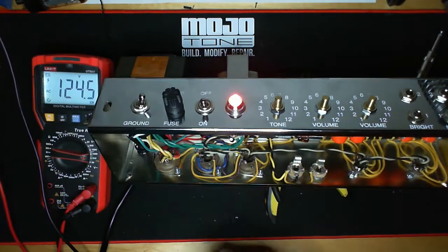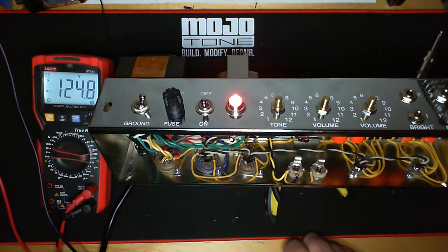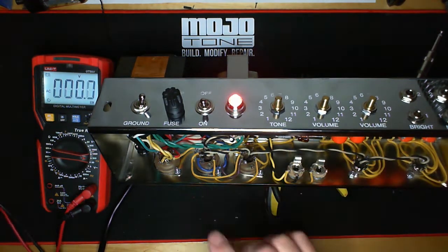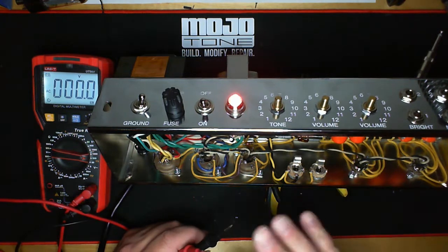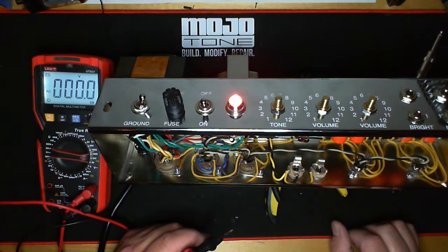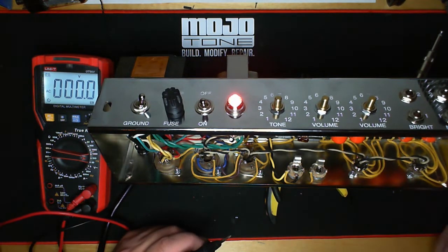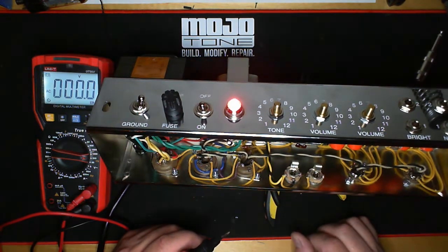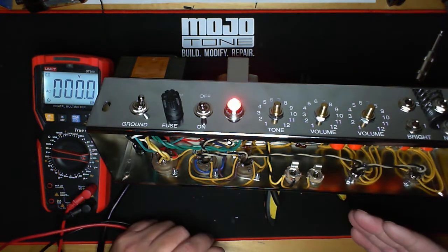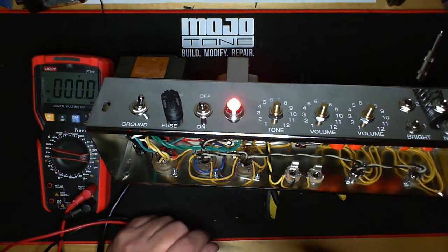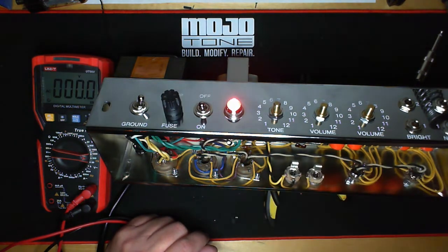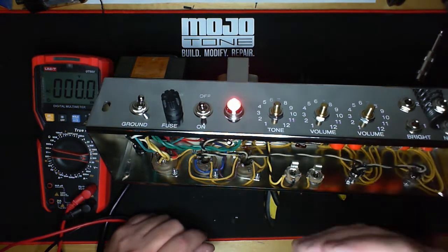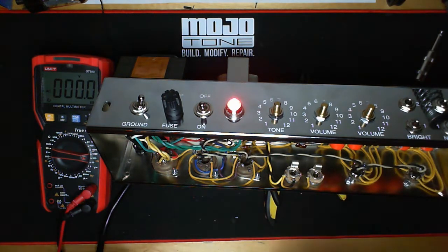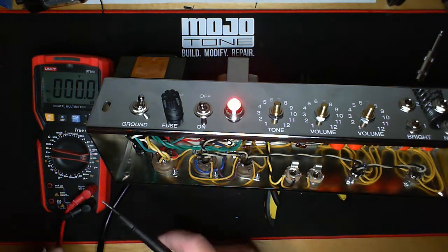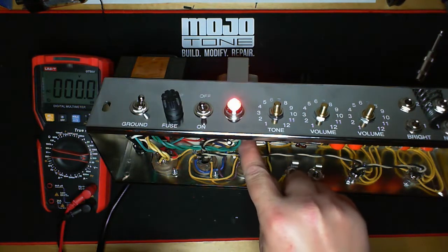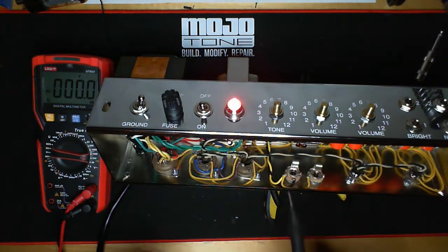I run almost 125 volts here, so that's going to elevate everything on my secondaries, and I need to be mindful of that when I'm looking across the board. That basically means that already, because the voltages are unloaded, they're going to be 10% higher than what they are. Then add an extra 1-2% because I'm about 5 to 6 volts over where I should be for 120 volts. This is very common, we get a lot of calls about this, and when we get the rectifier in, it'll become even more obvious.